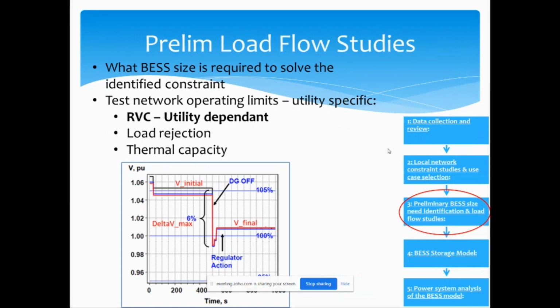Having that size in mind, you now want to perform some tests to check the network operating limits. It's easy to say I need 10 megawatts, 50 megawatt hours of storage on a certain part of the network to solve my problem, but you also need to balance that with the network operating limits, which are utility specific.